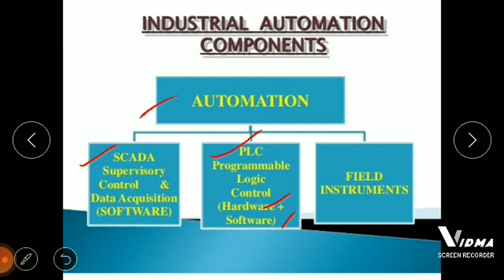Automation, earlier, we were using this approach, from downward to upward, we can say. So sensors are placed in the field. If you want to measure some information from the real world, you have to put the sensor there in the field. Then these sensors are connected with field cabling to a junction box, where a number of inputs are connected at the same terminal. Then the junction box, with field cabling, is again connected to our control hardware, that includes our PLC, SCADA and PID controller. And finally we put all these things on the software. Software is related to the computer operations. So we process this information on the computer and make a decision for the final action in the process control.